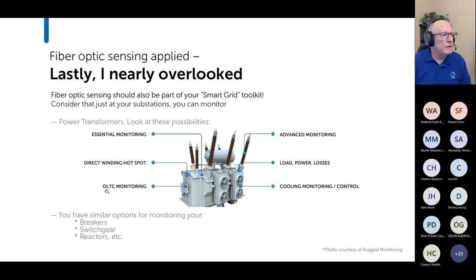You can monitor your load tap changer condition, the winding. You can look for hotspots in the winding inside the transformer. You can monitor the oil. You can listen for the sound of a partial discharge. All kinds of monitoring of the cooling controls, because of course those are essential for reliable operation of these transformers. You can do all of that. There are lots of possibilities. And you can do also breakers, switchgears, reactors, pretty much anything you want. There are a lot of fiber optic sensing options out there that are available today to help you monitor your equipment, with the goal of improving the reliable operation of your utilities' grids.